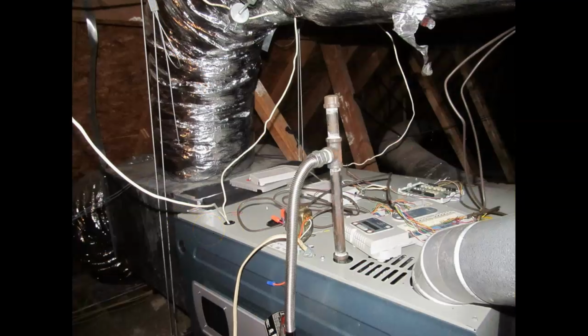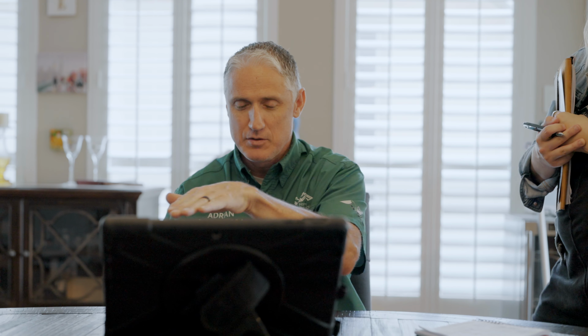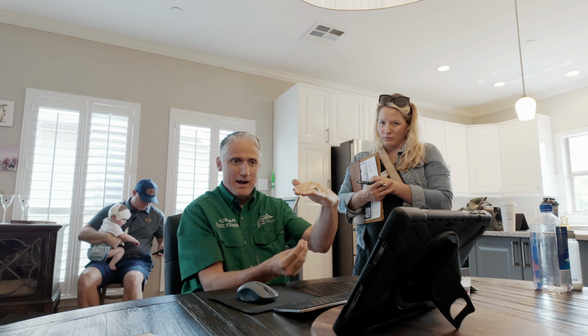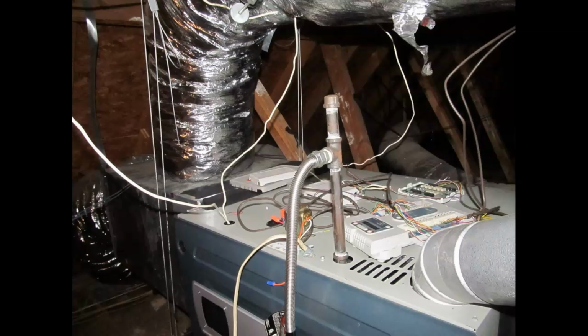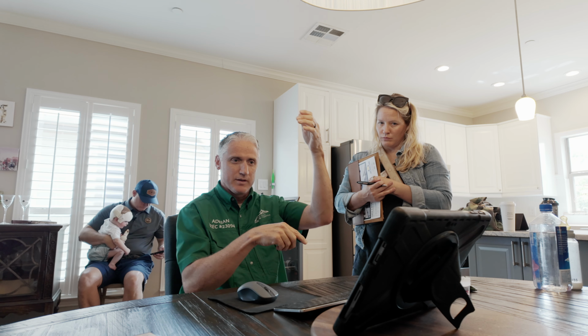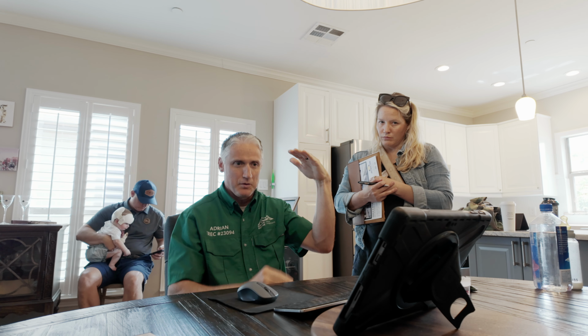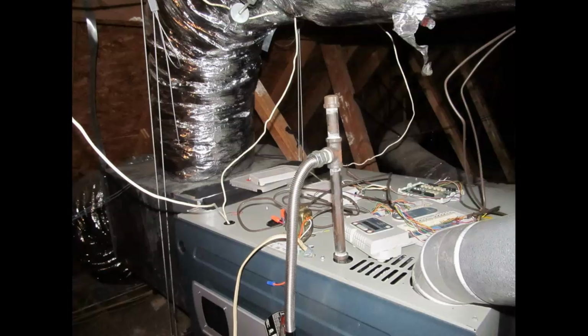So they did do this thing wrong. This is the gas line. What I'm specifically looking for is something called a sediment trap. As gas flows to the unit, this little piece of pipe should be down so that any debris or little bits or flecks of metal would collect in this pipe. But because they have it vertical, gravity is just going to pull those flecks down - so they just installed this upside down. Many homes don't even have that, it's a newer building standard, but since this was just installed, it's just not meeting my current standards.